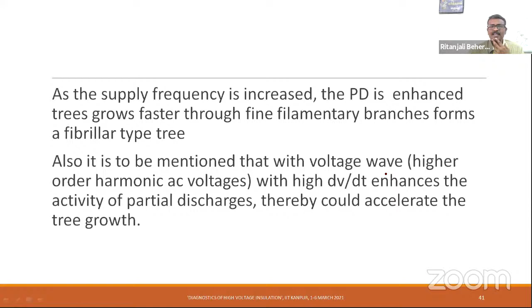The reason could be as the supply frequency is increased, the PD is enhanced and the tree grows faster through fine filamentary branches, and that forms more of a fibrillar type tree. And it is to be mentioned that with the voltage wave with the higher harmonic voltages, with a high dV by dt, this enhances the partial discharge activity. This could accelerate the tree growth. That is a little bit about the trees at the harmonic AC with harmonic frequency.